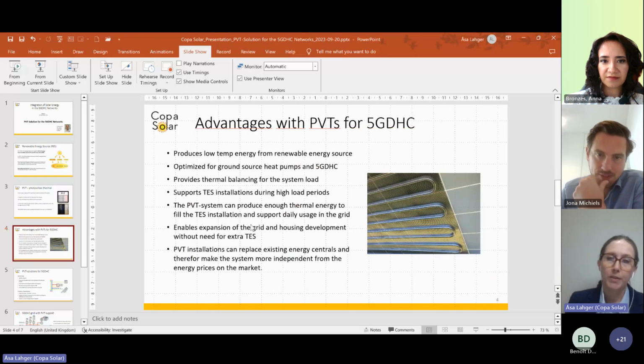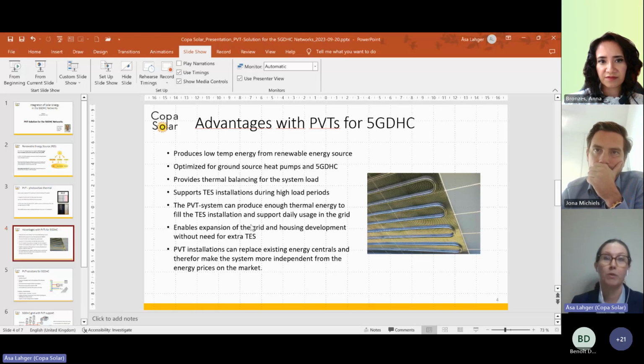What are the advantages of this kind of retrofit or new installation with PVTs? You still produce low temperature energy from a renewable energy source. The system is optimized for ground source heat pumps and therefore also for the 5G DHC grid. It provides thermal balancing for the system load, and supports the TES installations within the grid, especially during high load periods. In winter, when there's high demand for thermal heat, you reduce the amount stored in your storage, and you can revitalize the whole TES system with the help of the PVTs.